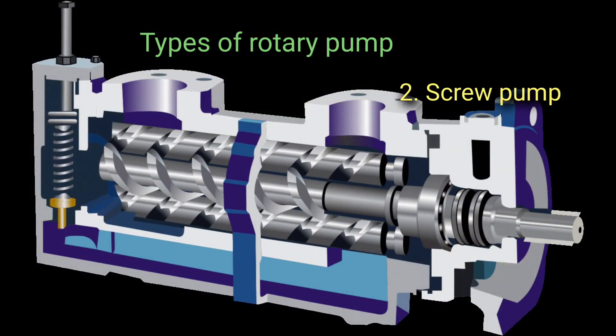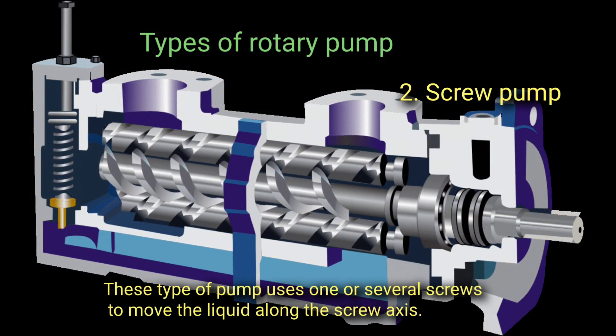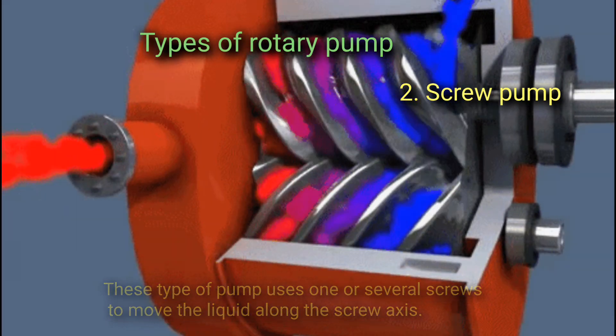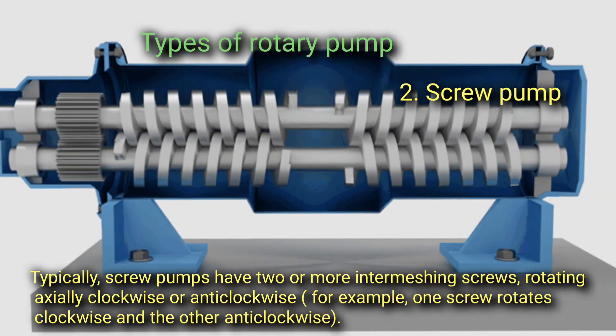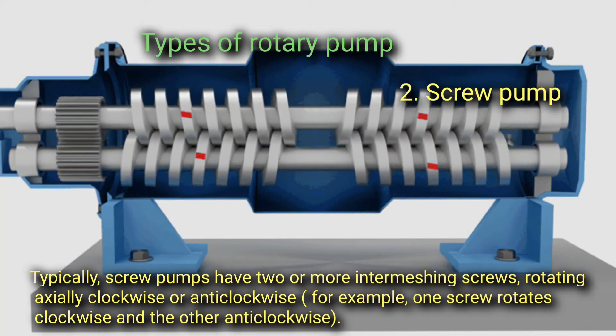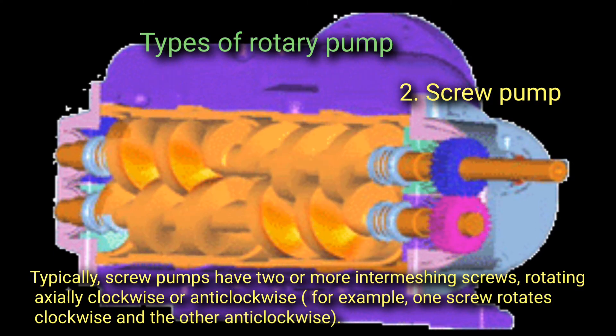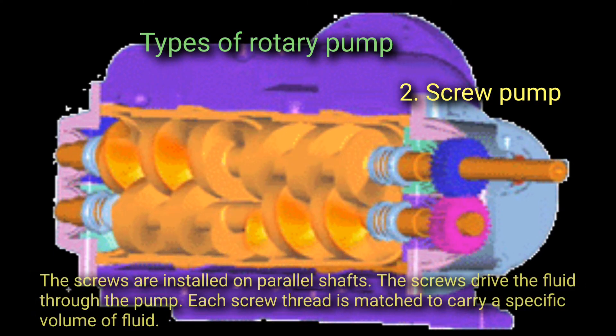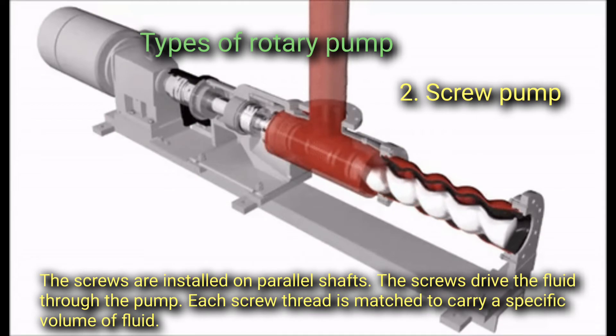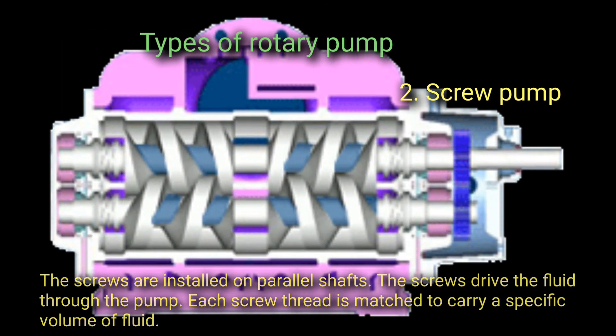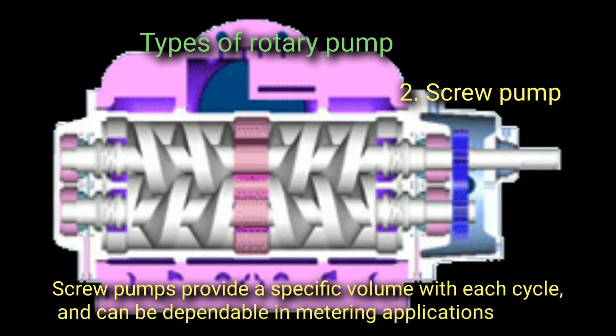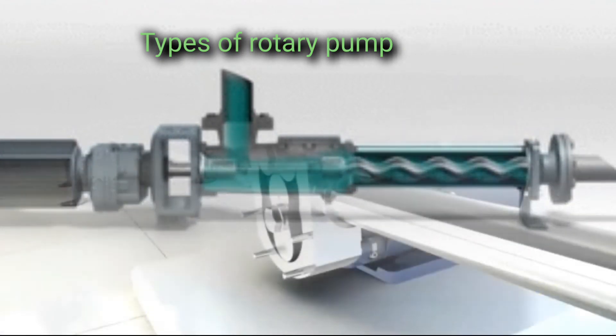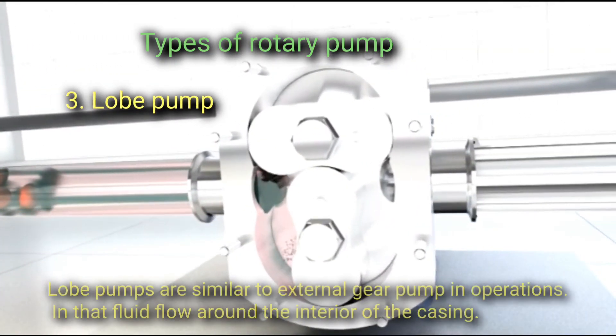Screw pumps use one or several screws to move the liquid along the screw axis. Typically, screw pumps have two or more intermeshing screws rotating axially — one clockwise and the other anti-clockwise — installed on parallel shafts. The screws drive the fluid through the pump, and each screw thread carries a specific volume of fluid. Screw pumps provide a specific volume with each cycle and can be dependable in metering applications.